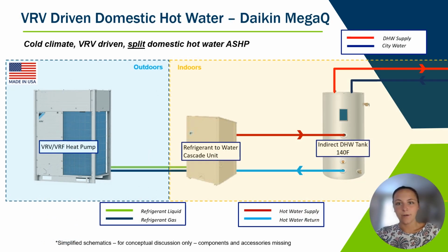And with that, we'll move on to talk about our VRV-driven split domestic hot water solution from Daikin called MegaQ. And as I mentioned, these systems will use our traditional cold climate VRV air source heat pump outdoor units, which will be piped with refrigerant piping to this refrigerant to water cascade unit. And these cascade units also have inverter compressors and a refrigerant to water heat exchanger, which will feed your domestic hot water tank.